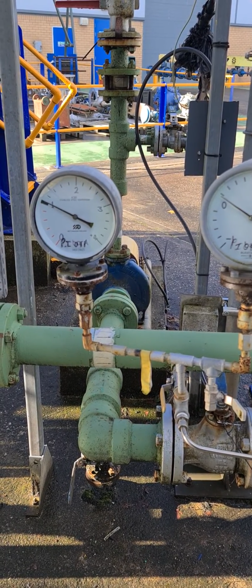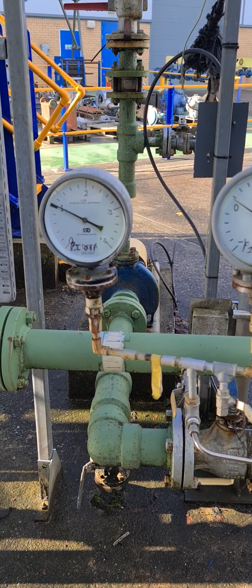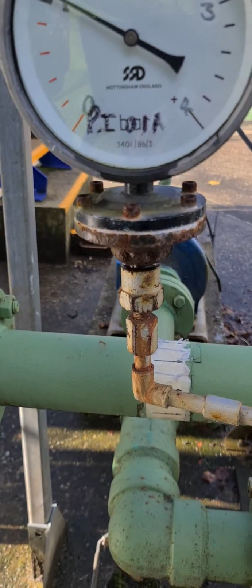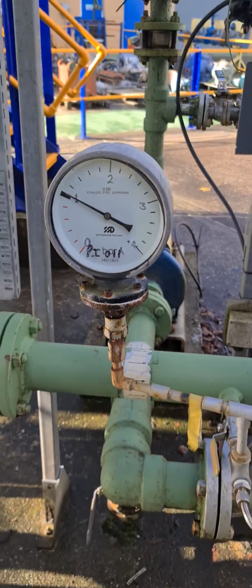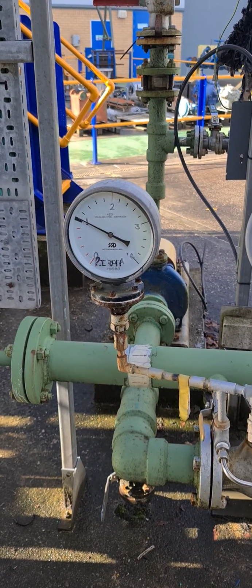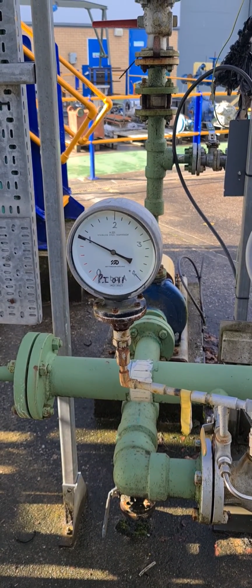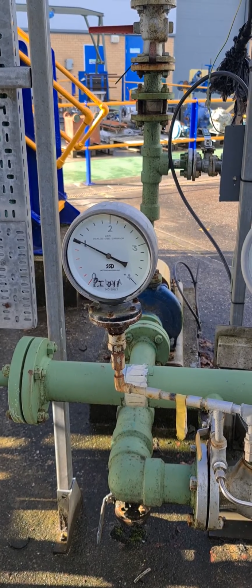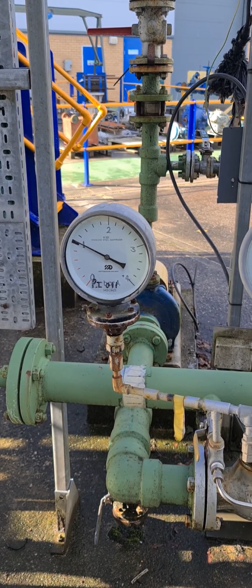As far as the measuring system is concerned, the conversion takes place at the diaphragm. The diaphragm simply produces movement, and this is the linkage inside the gauge that eventually shows the pressure reading on the scale.